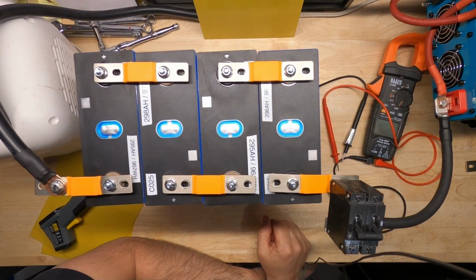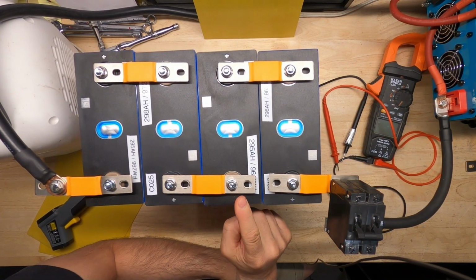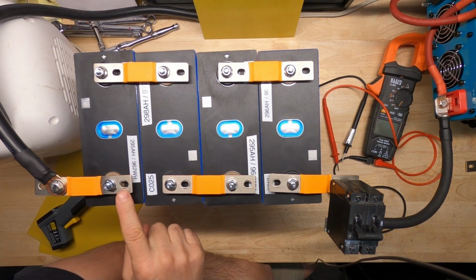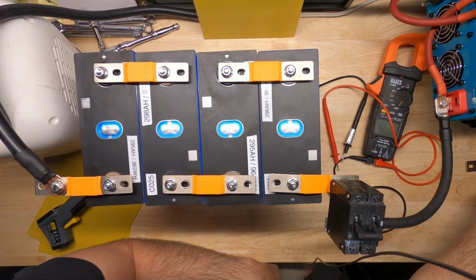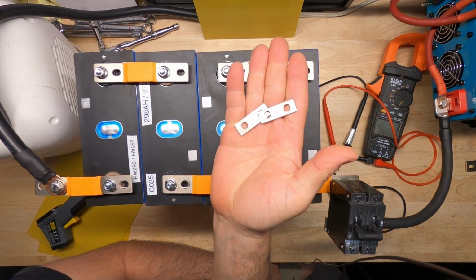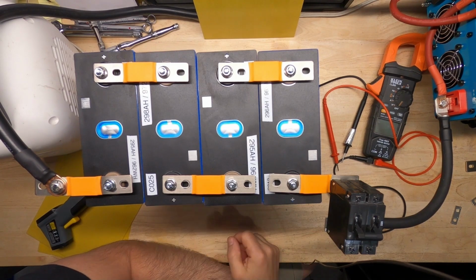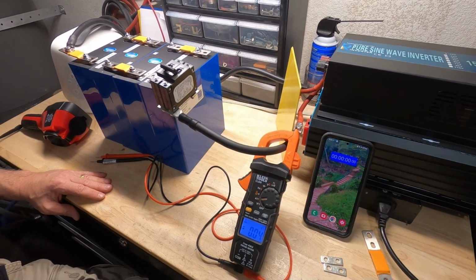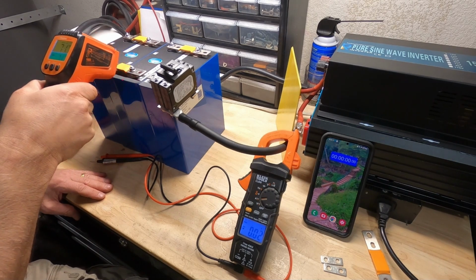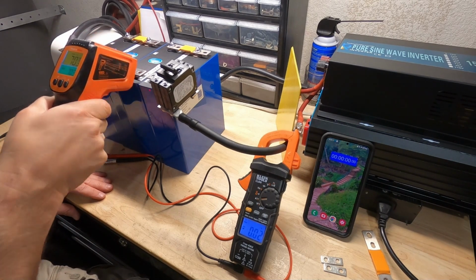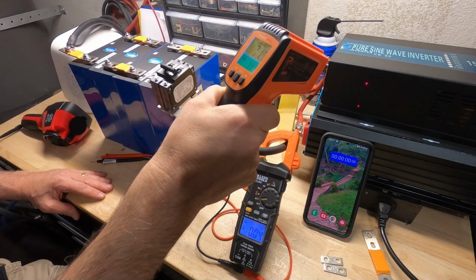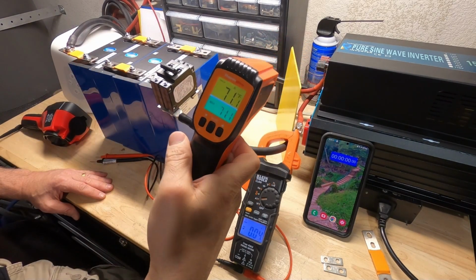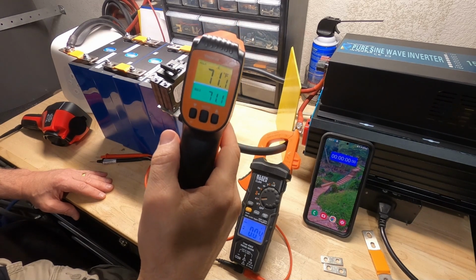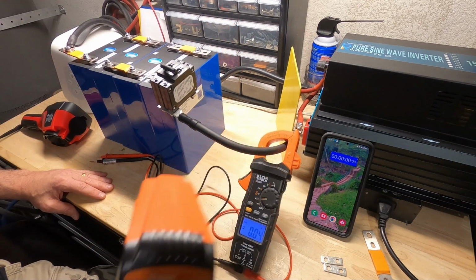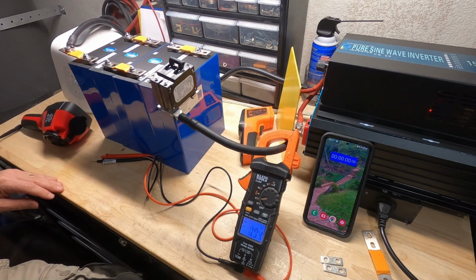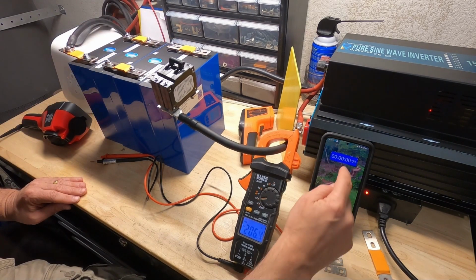Okay, so same as before, except we're using the single welded stud cells. We're using the flexible bus bars, and I have the 2 metal shims removed from the breaker. Okay, let's do an ambient temperature check. 70 degrees on the batteries, breaker, inverter, and we're sitting at 72 in the room on the thermometer up there on the wall. Okay, let's go.